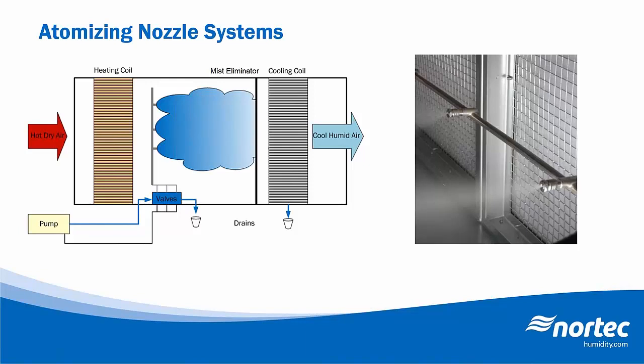So typically with this type of system, any unevaporated water that comes off of the droplet separator will get sent directly to drain. So it's important to ensure that these systems are designed properly to ensure the highest possible evaporation efficiency and minimize the amount of wastewater. So we typically try and design these for an evaporation efficiency between about 70 to 85%. Now, depending on the design of the water system itself, the water coming off the droplet separators can sometimes be reclaimed and run back through the water treatment in order to help reduce the overall water usage of the system.